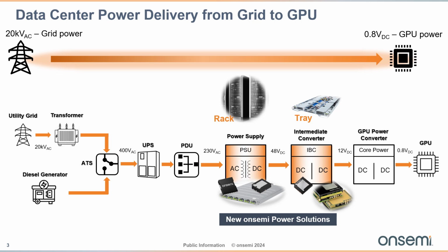Total rack power until few years ago was around 30 kilowatt. However, with future AI data centers demanding more power up to 100 kilowatt at the rack level, power solutions of the past fall short. Today, we highlight onsemi's latest solutions that are used in power supply units and intermediate converters in the server rack. onsemi's latest generation M3S 650 volt MOSFETs and T10 silicon MOSFETs in 80 volt, 40 volt, and 25 volt are used in the power conversion from AC to DC and also intermediate bus converters.